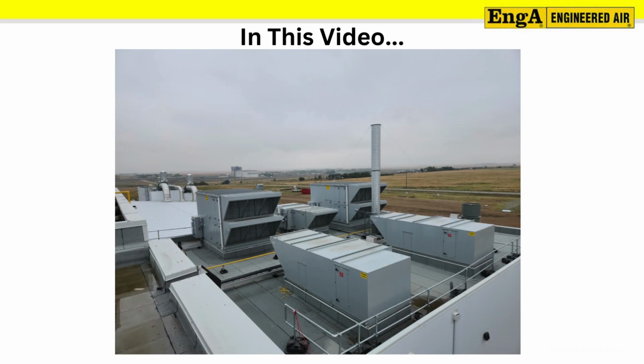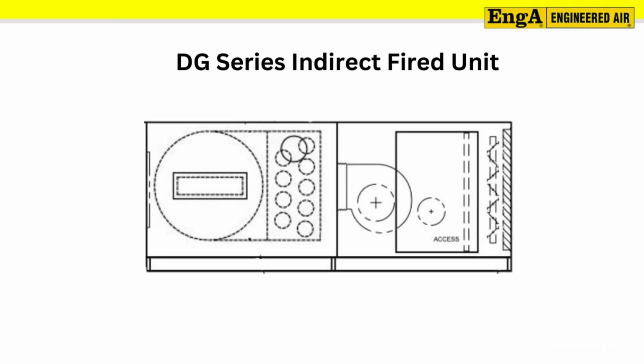In this video, we will cover the purpose of doing combustion analysis and the procedure taken to adequately set up the combustion on Engineered Air DG series equipment operated by a CenCon or base controller. Combustion analysis is performed on indirect fired equipment that uses a heat exchanger to separate its combustion gases from the air circulated within the building.